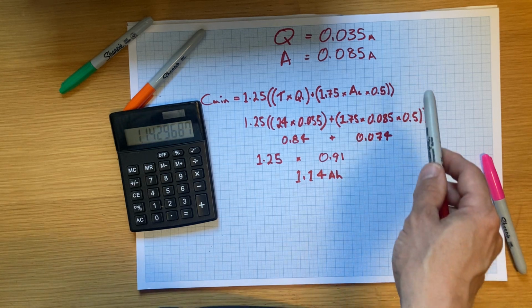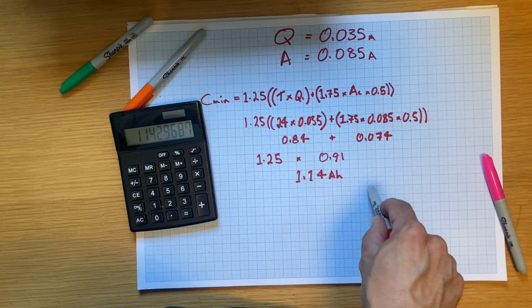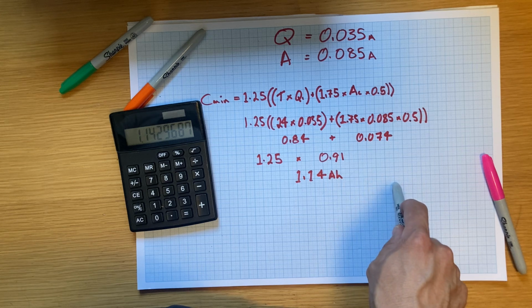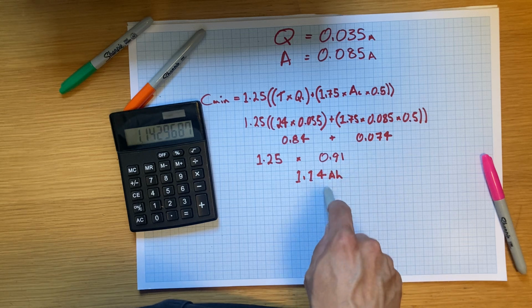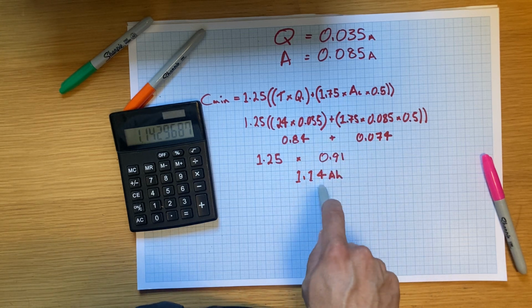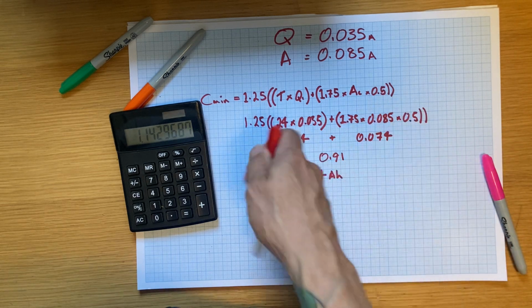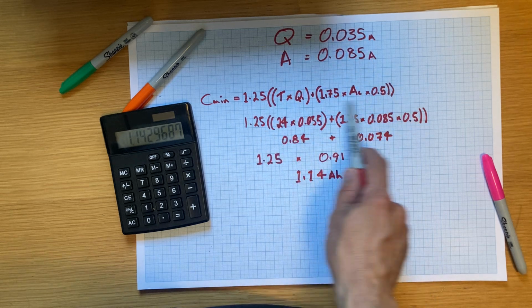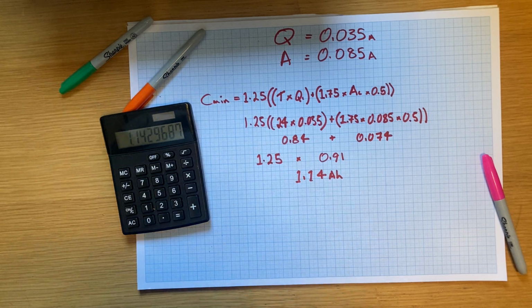But don't just stick the biggest ones in there without doing these sums, because that panel will run enough stuff that it would need 12 amp hour or 16 amp hour batteries. It's capable of doing that, but it's not capable of taking that size of battery. So if you know in advance what battery size the panel can take, that's good working out. But if you are taking over a site, you've measured your quiescent, measured your alarm, done your sums, and you can charge the client £1 million to sort out their battery situation.